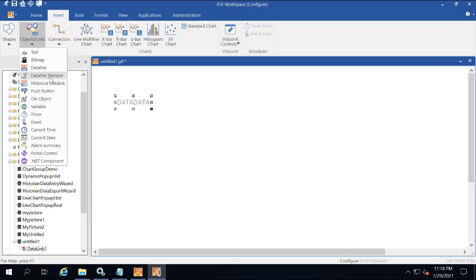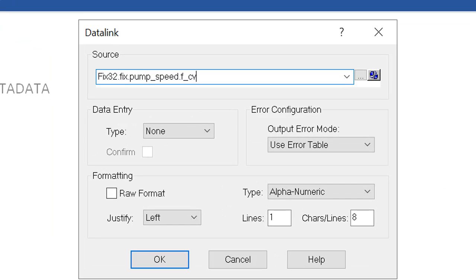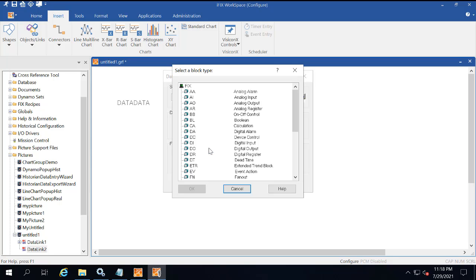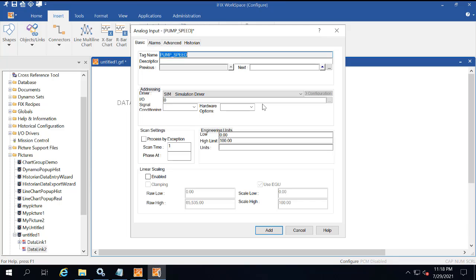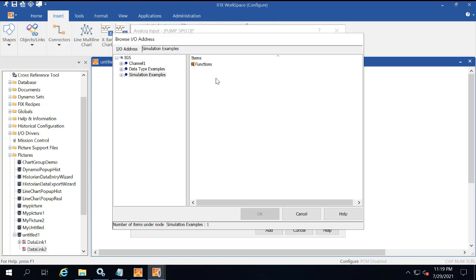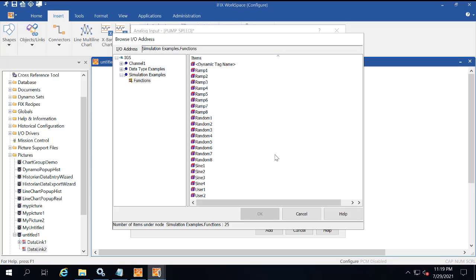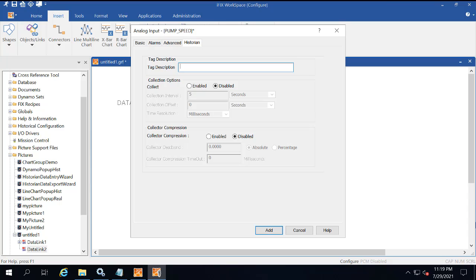Now we're just going to repeat these steps to create an AI tag. We're going to use fix32.fix.pump_speed.f_cv for the tag, create it, then add an AI block, an analog input. Browse to select simulation examples dot functions dot user two for the IGS IO address. You don't have to do the open and close label here. Just enable historian.